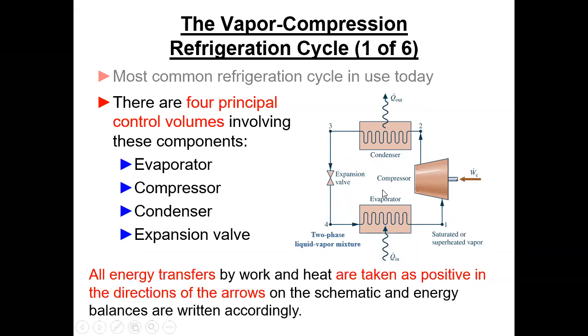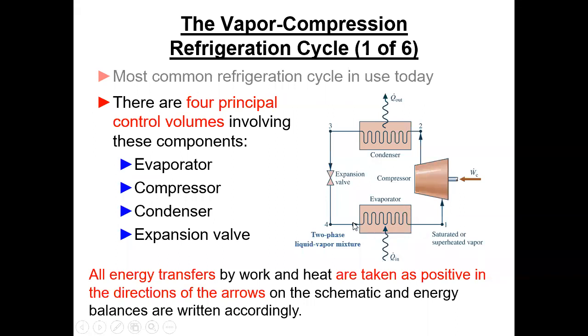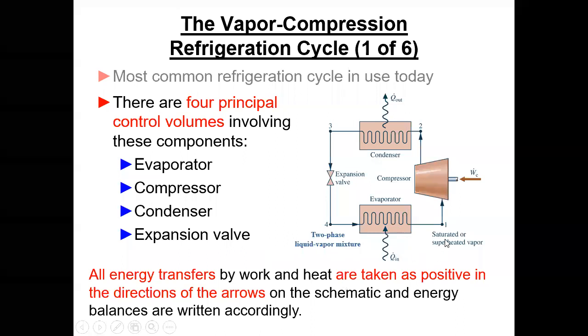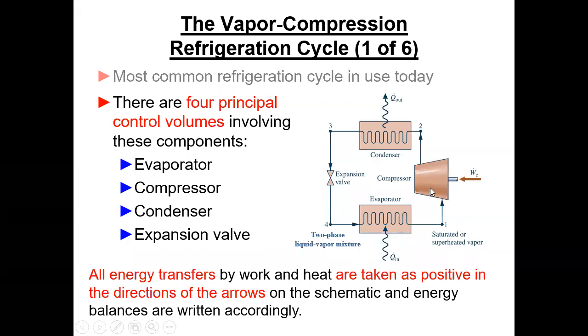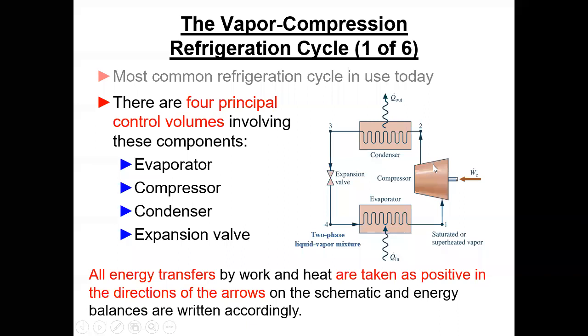For typical air conditioning, this supply air is typically 55, 56, 57 degrees — it's blown into your house and feels nice when it's hot outside. The evaporator does just that: it evaporates mostly liquid refrigerant at low pressure. Low pressure means low temperature, and we simply evaporate it to the vapor state. We may be saturated or superheated coming out — we sure don't want any droplets that would hurt the compressor — and then we compress up to the high pressure.